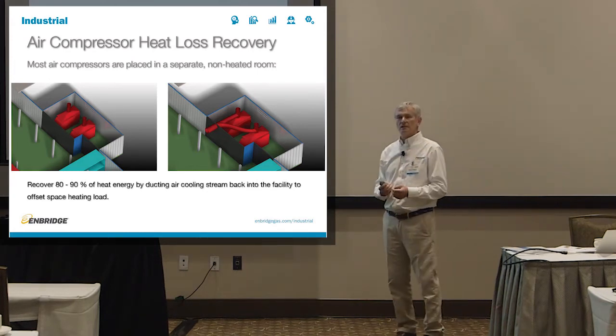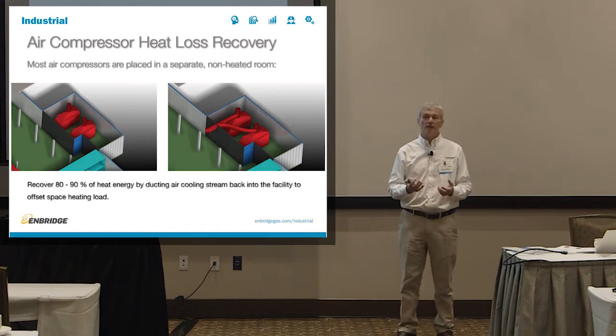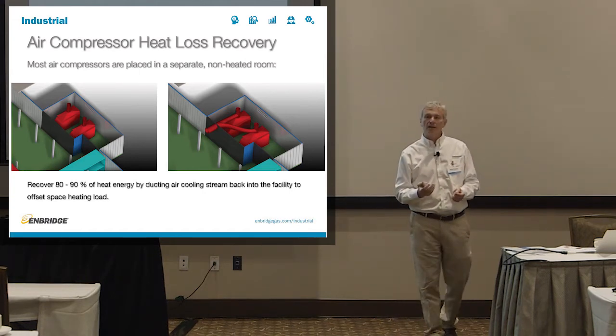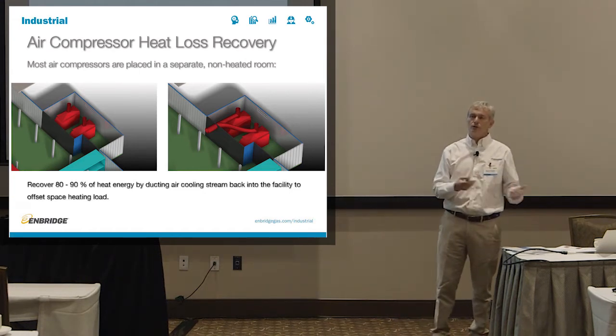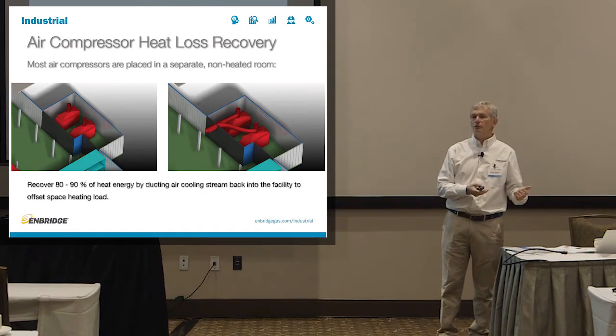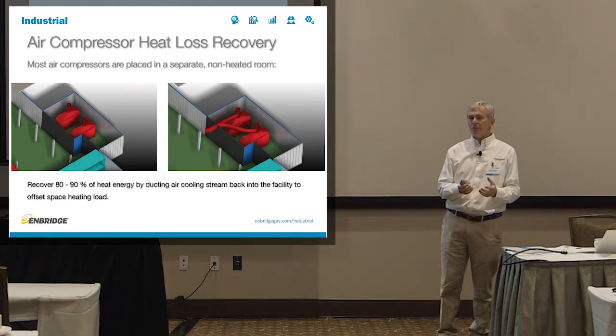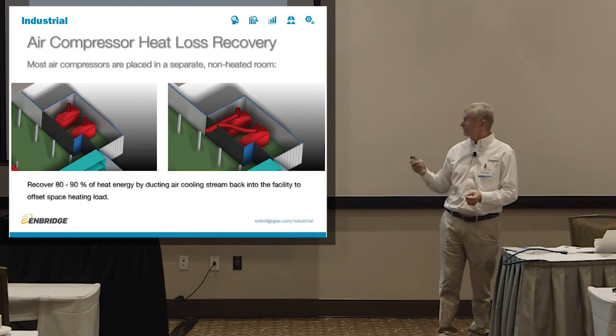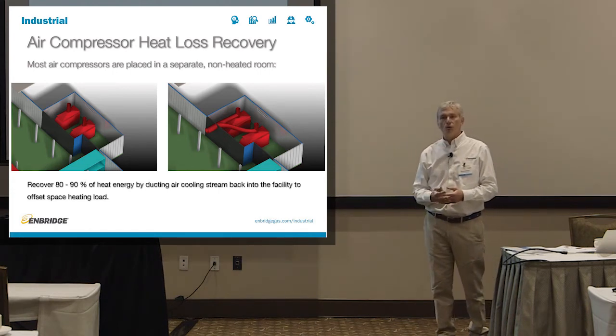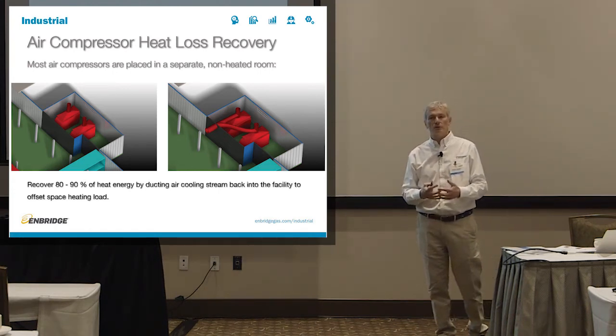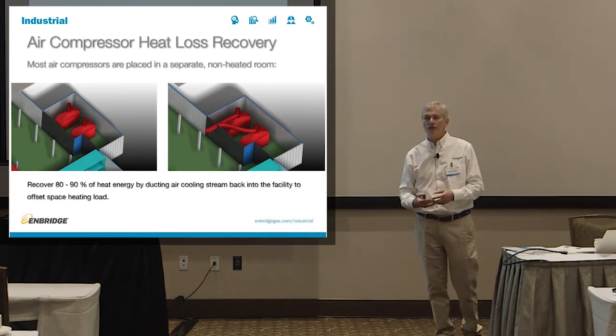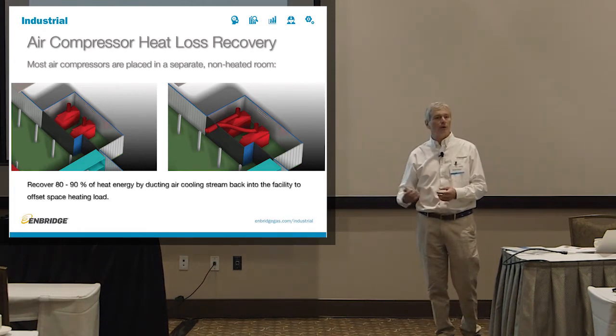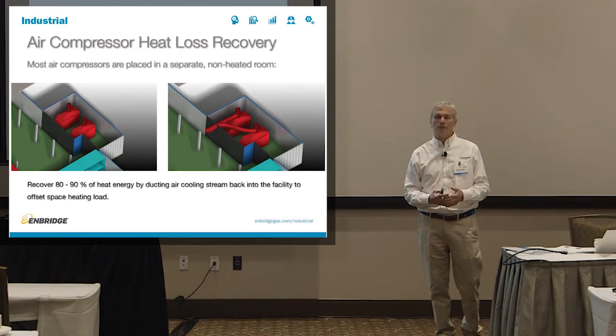So why not, instead of exhausting it, in the wintertime at least, put in ducting and put that hot air into the facility that sits right next to the compressor room. That will reduce your gas bill for the unit heaters or for your makeup air, and it will recover about 80 to 90% of all the energy you put into the compressor. So out of a 100 horsepower compressor, you can recover 80 horsepower as heat into your facility.